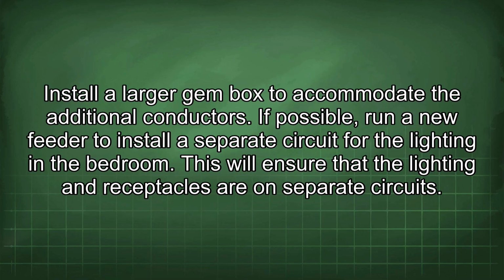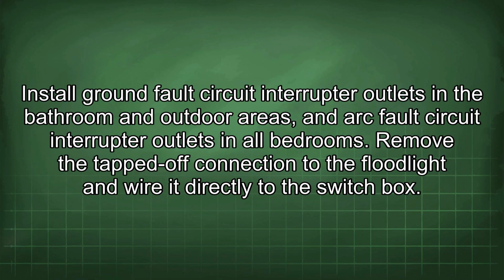Install a larger gem box to accommodate the additional conductors. If possible, run a new feeder to install a separate circuit for the lighting in the bedroom. This will ensure that the lighting and receptacles are on separate circuits. Install ground fault circuit interrupter outlets in the bathroom and outdoor areas, and arc fault circuit interrupter outlets in all bedrooms. Remove the tapped-off connection to the floodlight and wire it directly to the switch box.